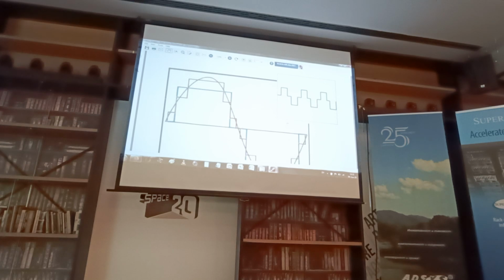Now it's possible that many of the low-cost UPSs, when you switch to battery mode, run on an inverter - they take power from the battery and convert it to AC power. When you do this, you won't have this black line. You'll have either the blue line, which we call a step wave, or this more sophisticated red line, which has a lot of little things.